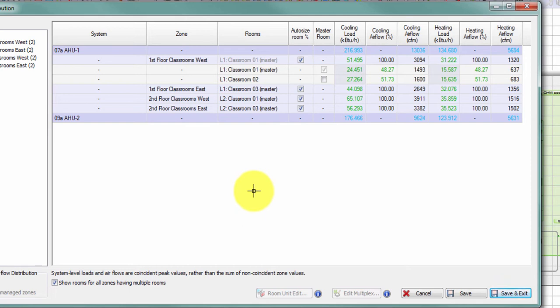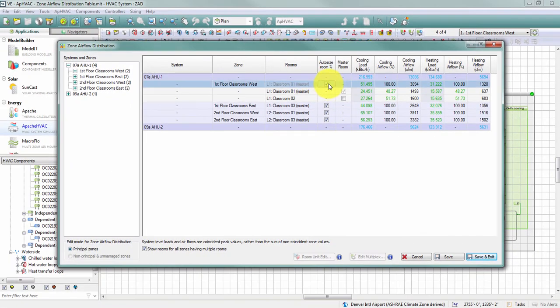By contrast, the cooling and heating loads for the system appear in light blue. Light blue values are derived and will be auto-sized unless the user unchecks the auto-size room percentage checkbox. Green or blue text turning black means it will no longer auto-size. Orange text indicates a local edit has been made. White or light-colored cells are editable, while darker shaded cells contain derived or auto-sized values not for editing in this dialog.